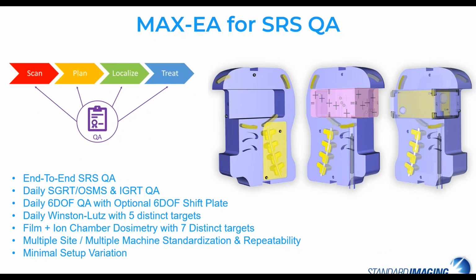So the Phantom that I'll talk to you about today is the Max EA Phantom, which is used for SRS QA and commissioning. For the entire process of end-to-end, there's this scanning of the Phantom, creating the plan, localization using the bony anatomy of the Phantom, and then delivering the treatment to the Phantom.